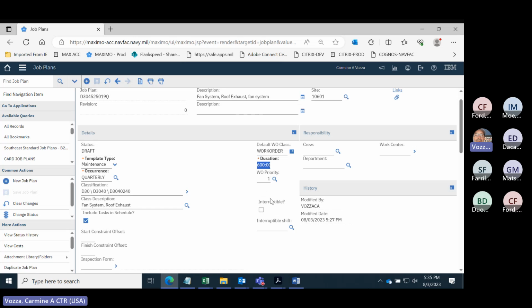Okay, so this is critical. Now, work order priority. I don't know where everybody stands on this, but basically we don't use numerical work order priority to tell me how important the work is. I have work type: emergency, urgent, routine. I have preventive maintenance work that has target completion dates. The priority from the shop's point of view is I look and see when I should be done with this work, and I push up the things that need to be completed sooner. That's my priority. We like to discuss using this, but we just don't.